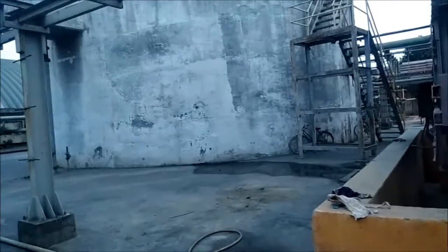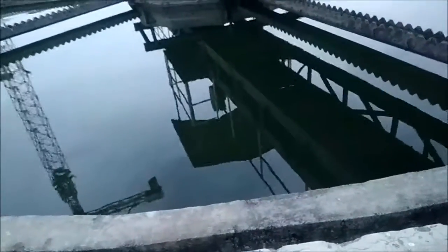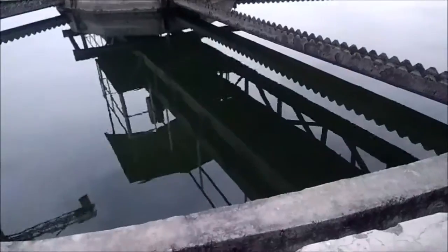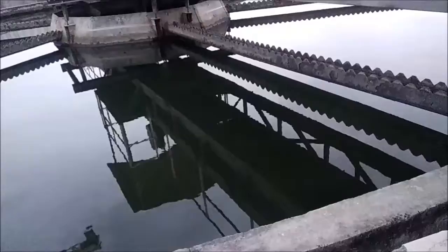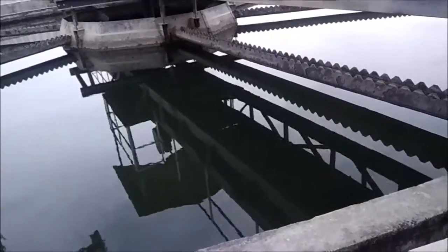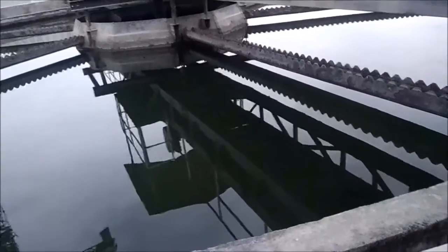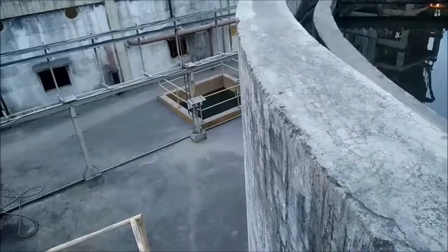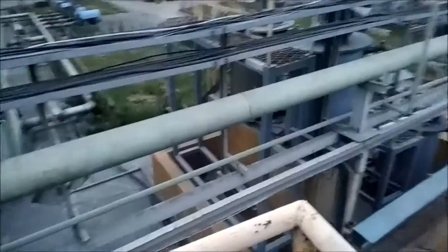Now this is called the SCR, solid clarifier reactor. You see, this is an agitator, a big agitator. Its function is to agitate the whole water inside this big tank, and the microparticles combine together to form macroparticles, and finally they form a sludge, which is then taken out from this tank. There you can see a small tank, that's the sludge. The sludge is taken out.